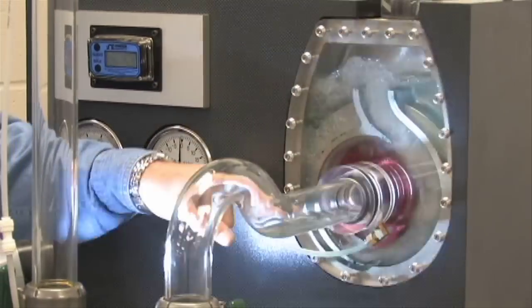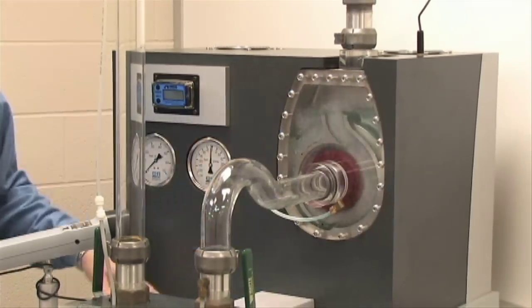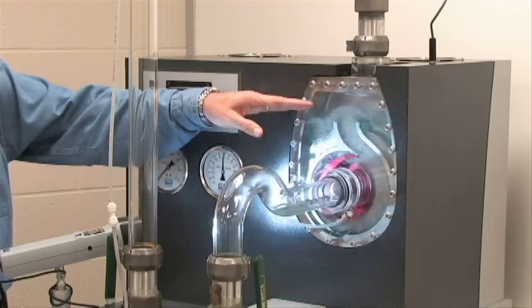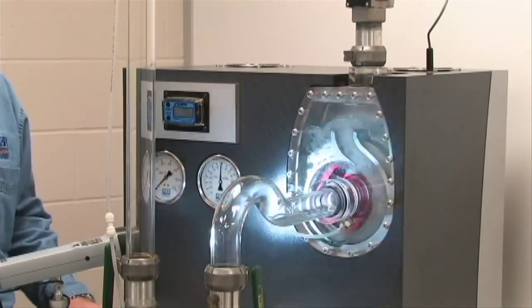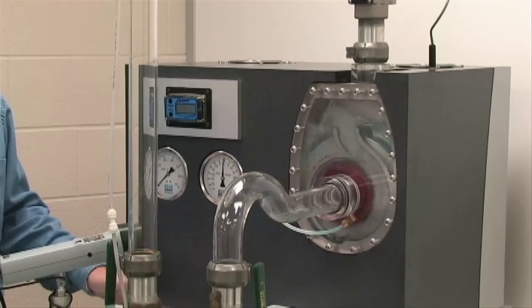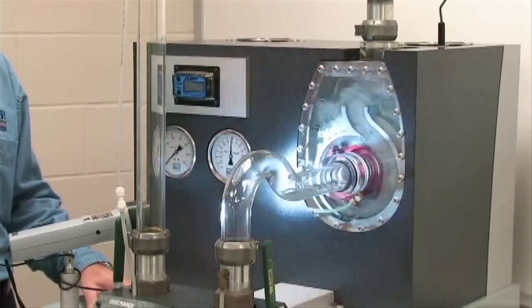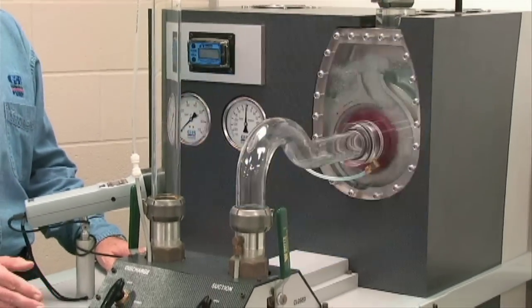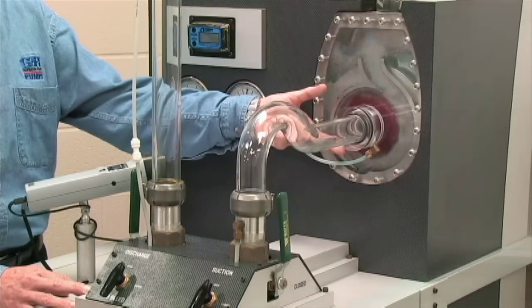All the while that we recirculate the water inside the casing and remove the air from the top, we create a low pressure at the eye of this impeller. Due to differential in pressure, atmospheric pressure that we live around every day is higher than the lower pressure created at the eye of this impeller.